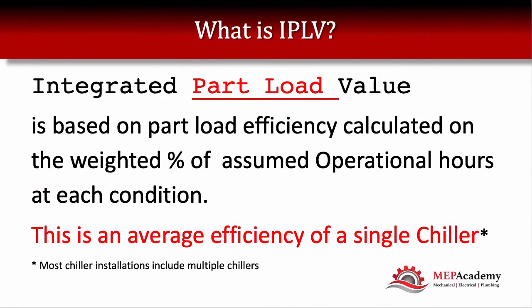What is IPLV? Integrated Part Load Value is based on part load efficiencies calculated on the weighted percentage of assumed operational hours at each condition. There are four points that are going to be measured. This is an average efficiency of a single chiller — most chiller installations will have multiple chillers, so this rating is for a single chiller.